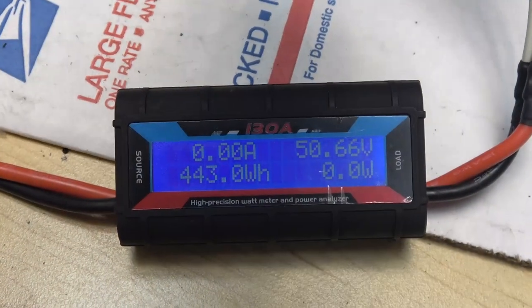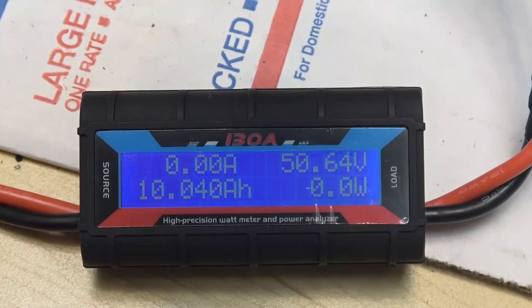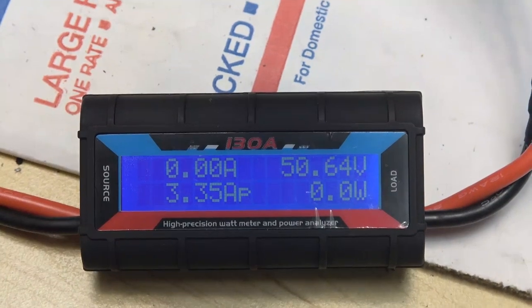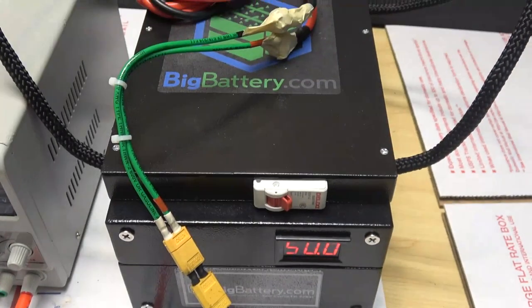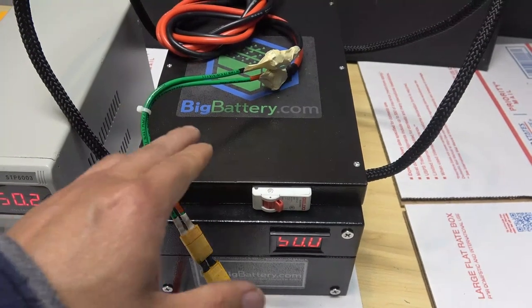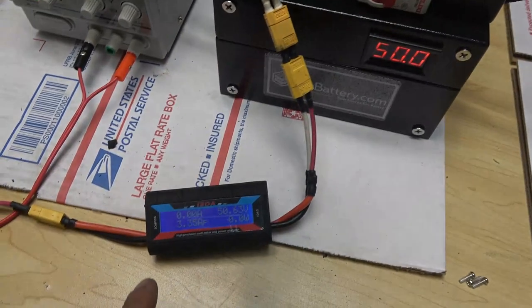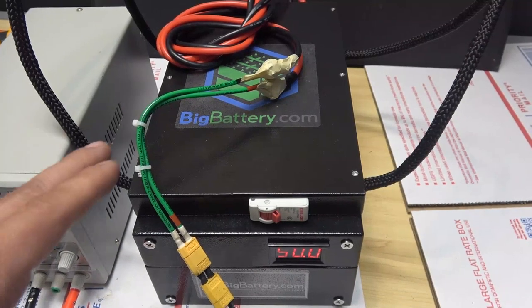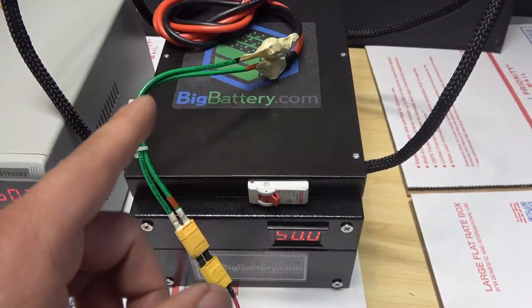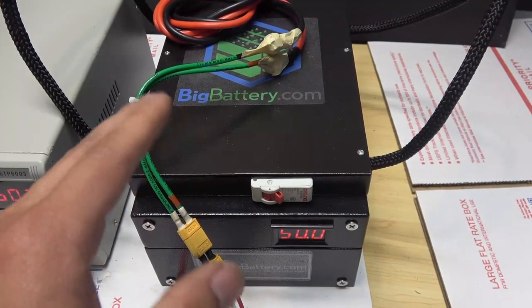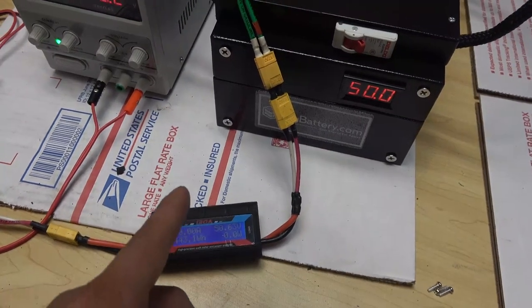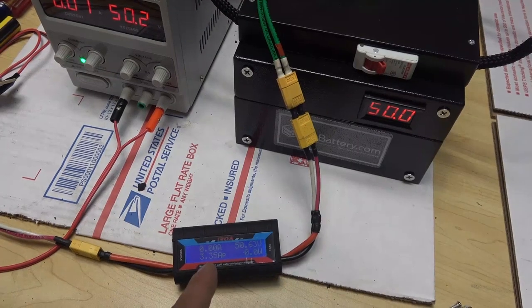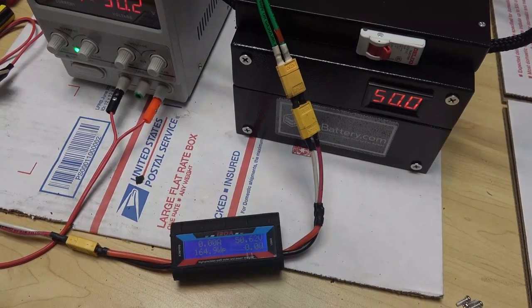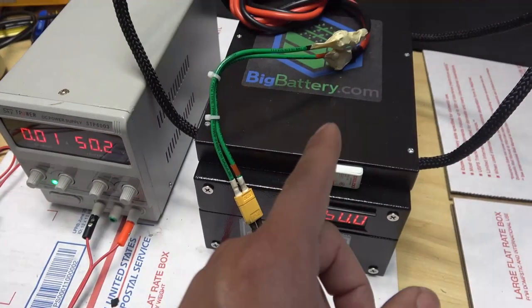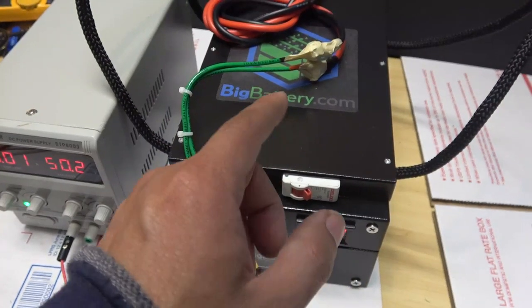Now take a look at the capacity meter. We've got 10 amp hour, or 443 watt hour, that has been put into this battery. The battery is rated at 500 watt hour, half a kilowatt hour, so 443 watt hour is very close. We have to remember we didn't charge the battery from zero - there was some residual power left, probably between 10 to 20%. Plus the amount charged in, almost 450 watt hour, that's about 90% of power charged into the battery, plus 10% residual power. So the rating on this battery is right on.